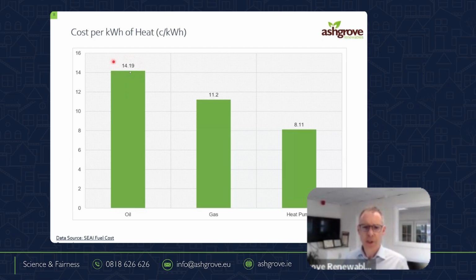But so compared to natural gas at 11 cent, a heat pump at a COP of, what have we taken here, 3.5? 3.5, yeah. Yeah, so kind of an average air to water heat pump or a poor geothermal heat pump would give us a COP of 3.5. So we're certainly cheaper. There's no question about that. And I've rammed that in early. Some of you mightn't still believe me when I say that, but that's a fact.